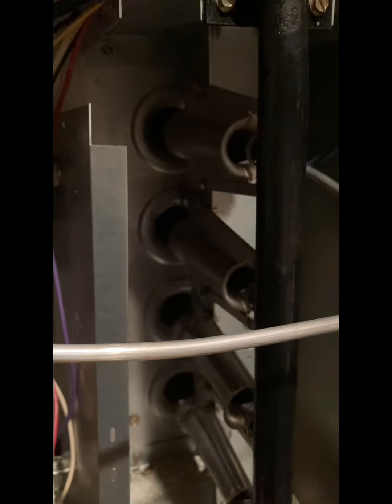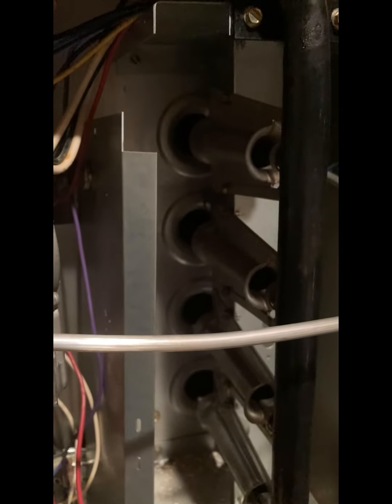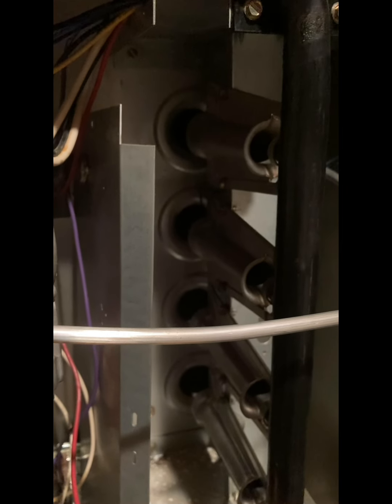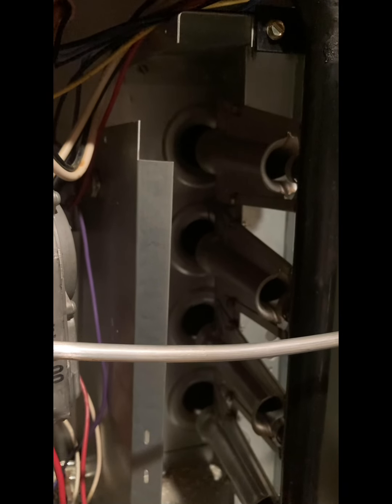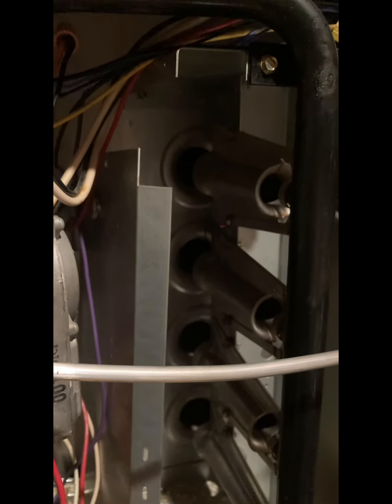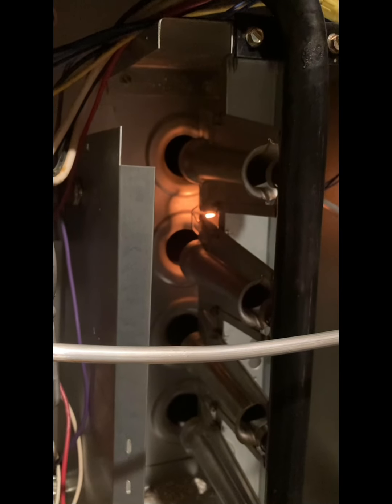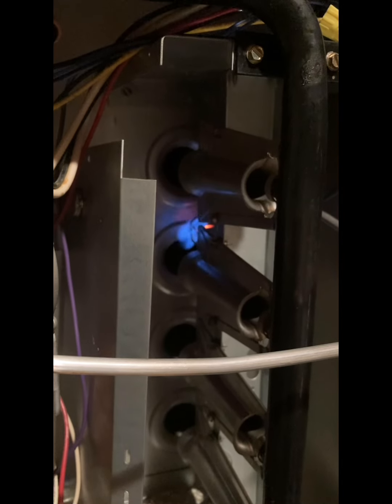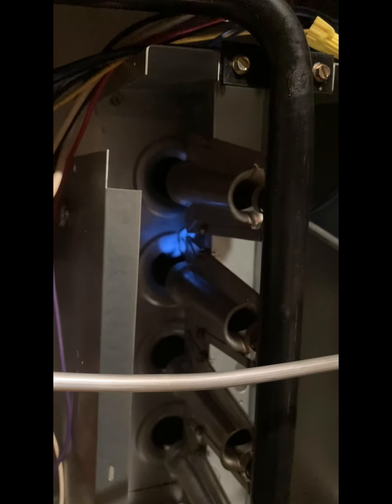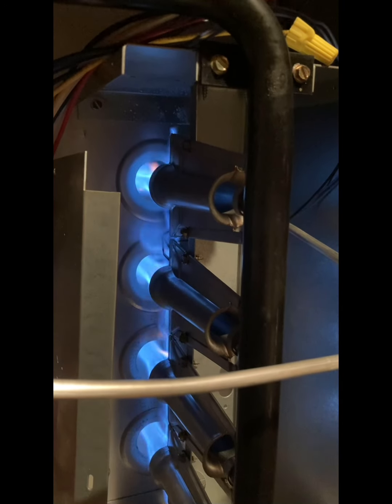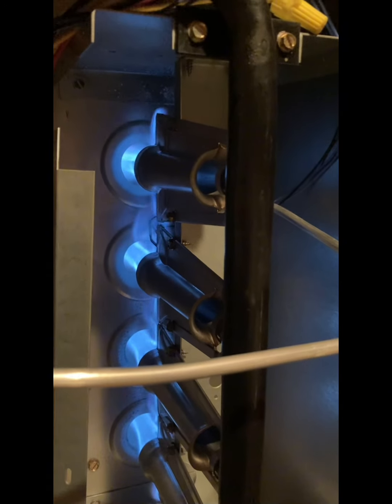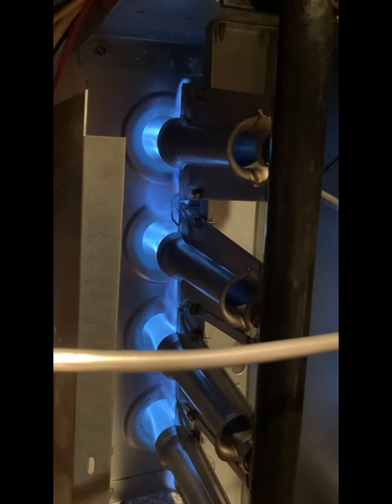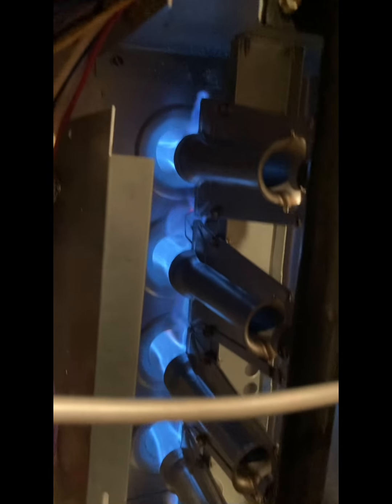So typically when I'm having an emergency call coming from someone, it's safe to assume that they're not a PM customer of anybody's, definitely not of yours, because you would have most likely caught this problem during a service call. So I'm typically coming into units that have never been serviced in 20 years, 15, 10, it's been a long time. And that first number 1 call is the flame sensor wins. Congratulations, dirty flame sensor. I see this by running sequence when I get onto a unit, and I'm watching it go through the sequences. Gas valve opens. I'm watching the flame come on. The flame's only on for like 15, 20 seconds, and then bada bing, bada boom, I lose flame. And then it just does the whole thing over again.